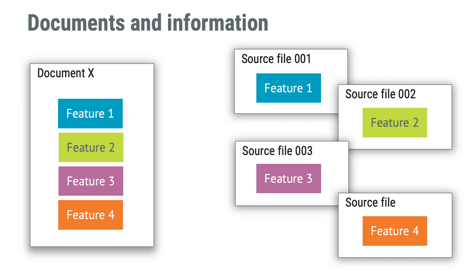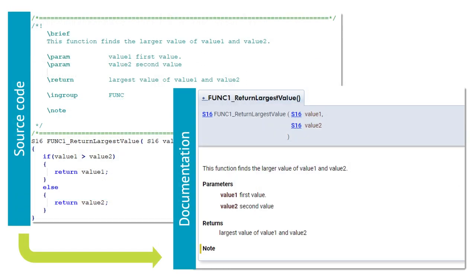Either you keep the information in the source file, or you decide to extract it and create traditional documents. Your way of working with information and documents can be explained in the software development plan — there is certainly no need to convert all information to paper documents, but you need to identify where it can be found and how you control it. For example, using Doxygen format for comments means that if you really must, you can also easily extract the comments to traditional document formats. When you later maintain the code, the documentation is available where it supports the developer the most and is much easier to maintain. If you take this one step further, technical documentation can be an integral part of your build process by creating a build pipeline for documentation running in parallel with your software build — ensuring documentation is always in sync with the software.